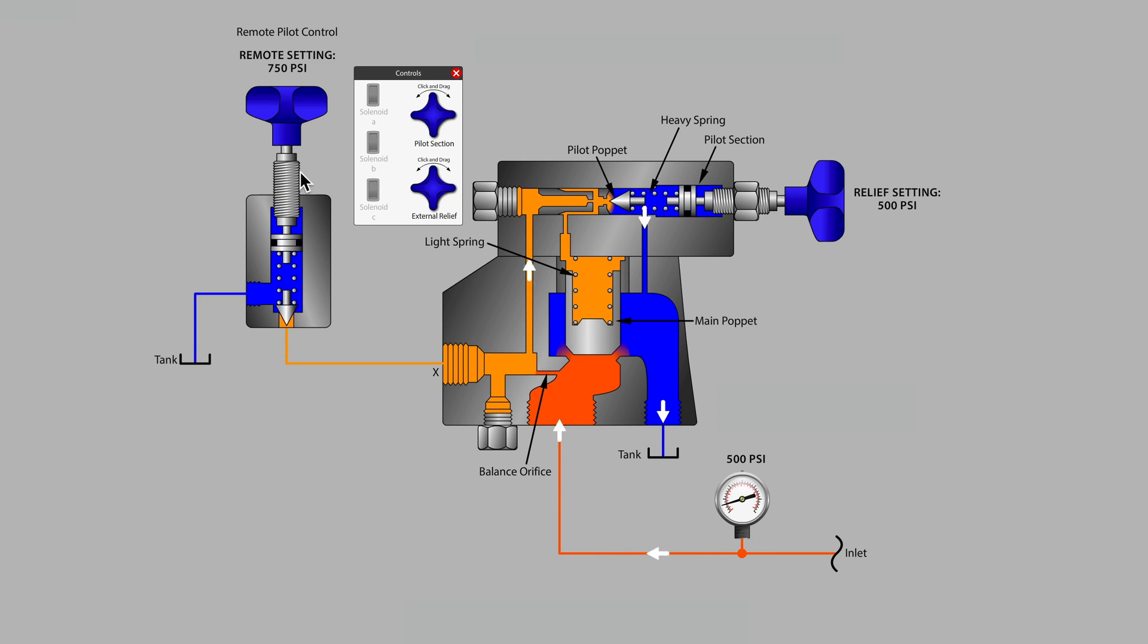Right now our system pressure gauge shows 500 psi, and that is the setting of the pilot section on the main relief valve. So clearly the pilot section on top of the relief valve is controlling system pressure at the moment.